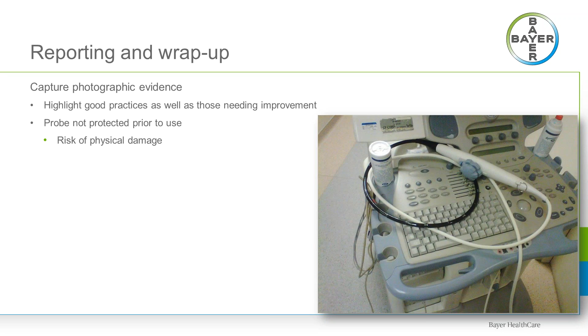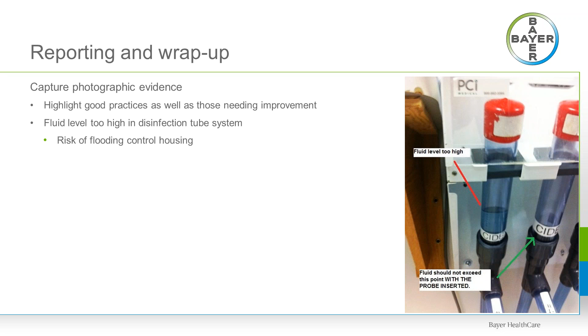A tube system for disinfection has been around for 10 to 12 years, and it's still an acceptable tool. The challenge with a tube system is, as mentioned earlier, the level of the liquid needs to be monitored and kept at a safe level. If we look at the levels of liquid in those two tubes, it's possible for users to flood a probe and not even realize that it's occurring. They're just immersing the probe in the liquid.